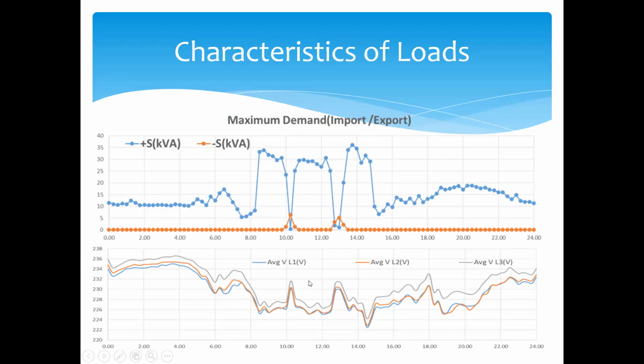This one is from a transformer in the Kakirav area. You can see the blue is importing, the red one is exporting. Like before, this is the 15-minute average import and export maximum demand. Around 10:30, the transformer has changed its mode from import to export. Again, around 1 o'clock, it has changed its mode from import to export. When I checked the load curve for several days, I found the same thing repeating. And I wanted to know why these changes are there, because it repeats every day.